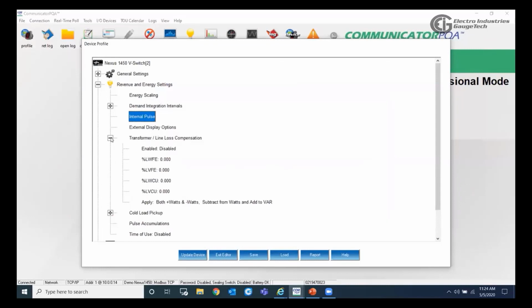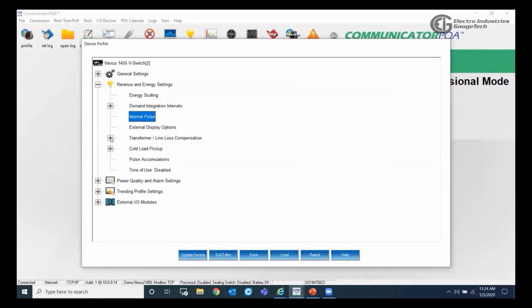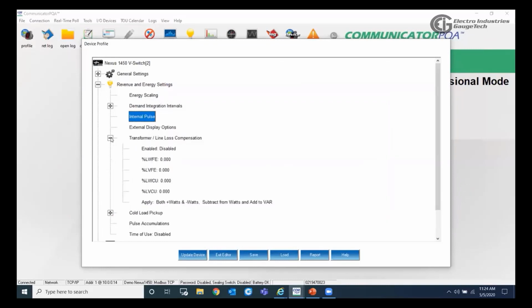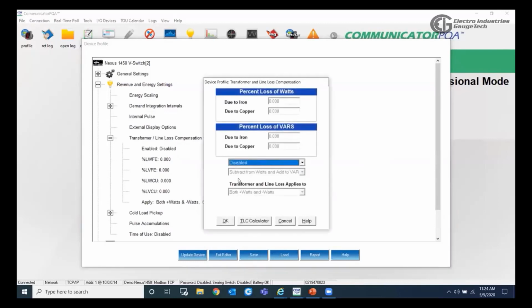We have also this option where we can enable the transformer line and loss compensation. This meter can calculate the transformer or the line compensation losses, and they can be added there and deducted from the energy. So you can enable that from here by choosing if it's for FE only or CU only, or both of them.